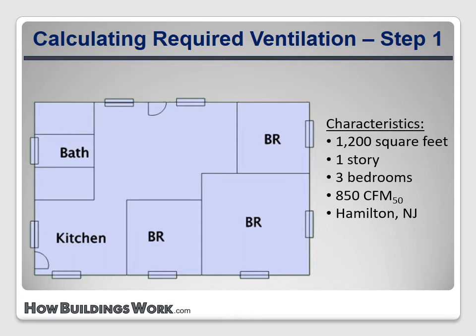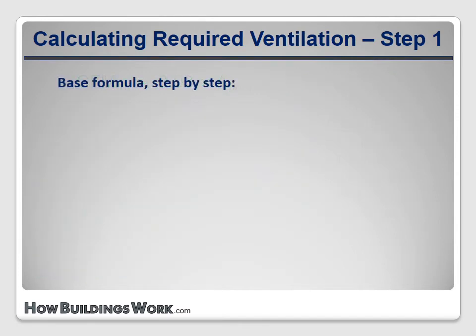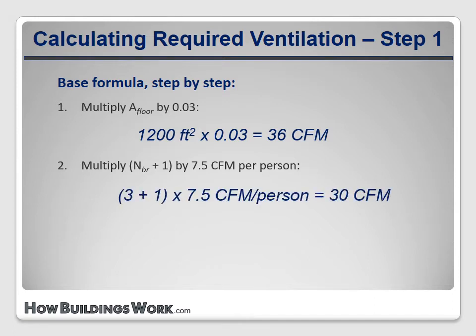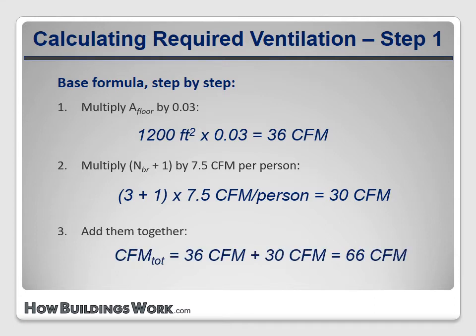Our first step is to plug the information into the formula for the total desired ventilation rate. The first part of the equation deals with the floor area, so we multiply 1200 square feet by 0.03, giving us 36 CFM. The second part deals with the number of occupants: we multiply three bedrooms plus one — four potential occupants — by 7.5, giving us 30 CFM. So we need 36 plus 30 for a total of 66 CFM of desired ventilation.